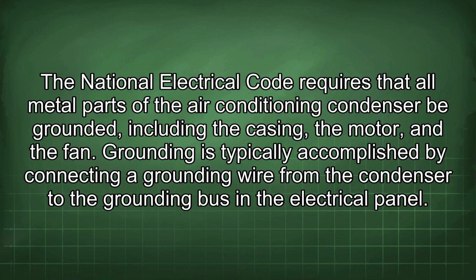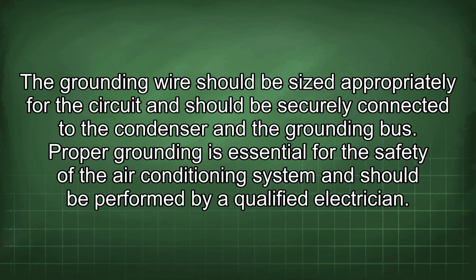The National Electrical Code requires that all metal parts of the air conditioning condenser be grounded, including the casing, the motor, and the fan. Grounding is typically accomplished by connecting a grounding wire from the condenser to the grounding bus in the electrical panel. The grounding wire should be sized appropriately for the circuit and should be securely connected to the condenser and the grounding bus. Proper grounding is essential for the safety of the air conditioning system and should be performed by a qualified electrician.